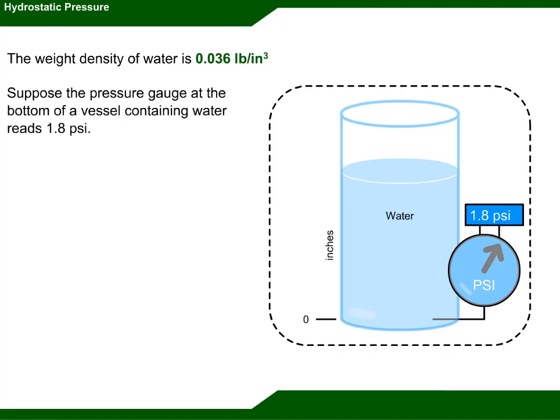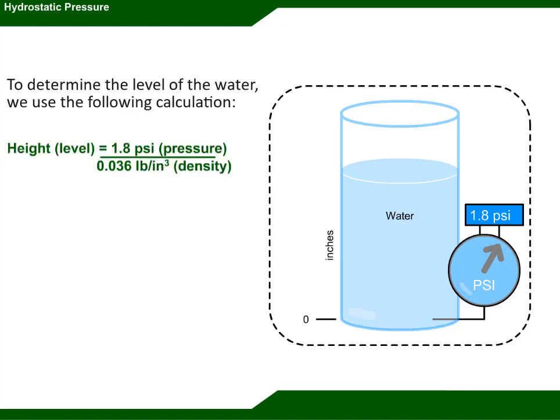Suppose the pressure gauge at the bottom of a vessel containing water reads 1.8 psi. To determine the level of the water, we use the following calculation: the height level equals 1.8 psi divided by 0.036 pounds per cubic inch.